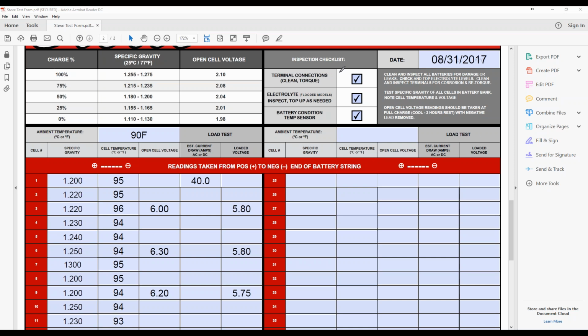We have a checklist. Make sure you clean and torque your terminal connections. Use a torque wrench. Get a torque wrench. They're not that expensive, and they're well worth the investment. If you don't have a torque wrench, that's one of what I call the Goldilocks rules that apply to batteries: too tight, too loose, just right. When you start noticing that the washer is biting into the terminal, you're probably too tight. If you notice that the terminal temperature is hotter than the rest of the terminals, then it's probably too loose. So it's a good idea to have an IR temp sensor. You can get them for 25 bucks at Lowe's or Home Depot or a hardware store. That way you can check those out.